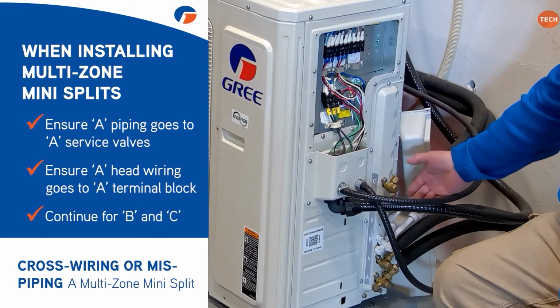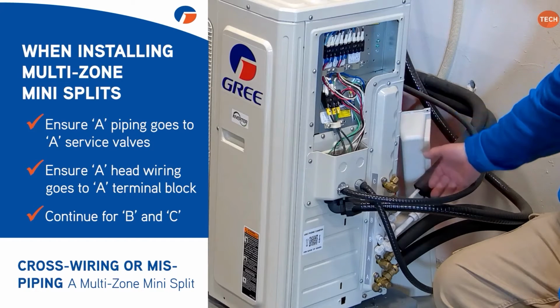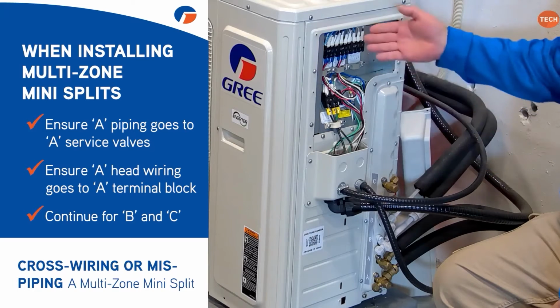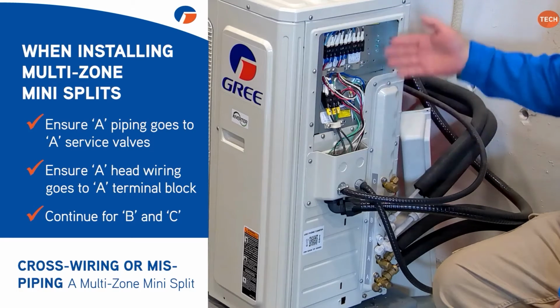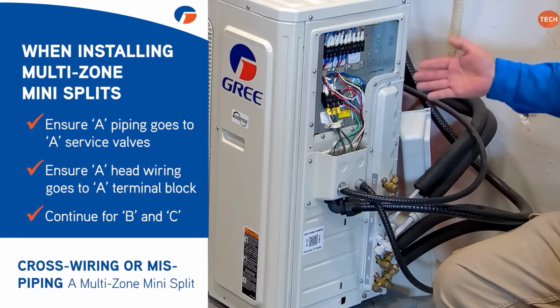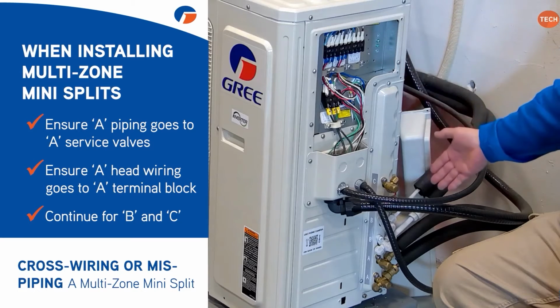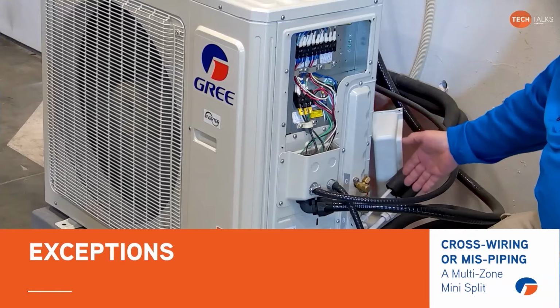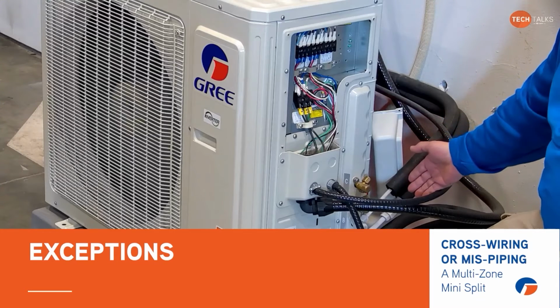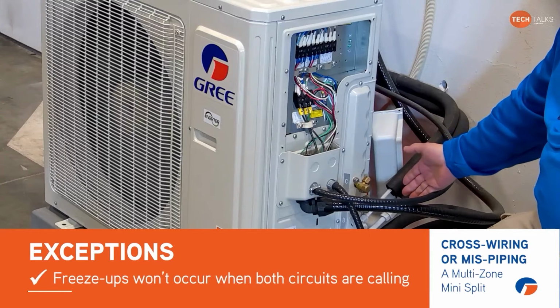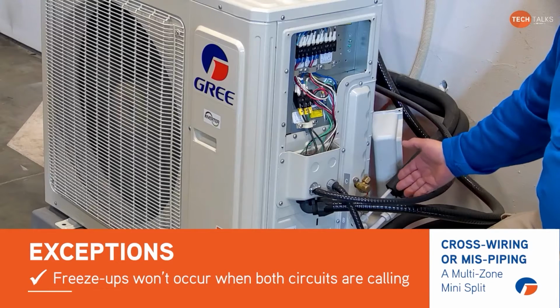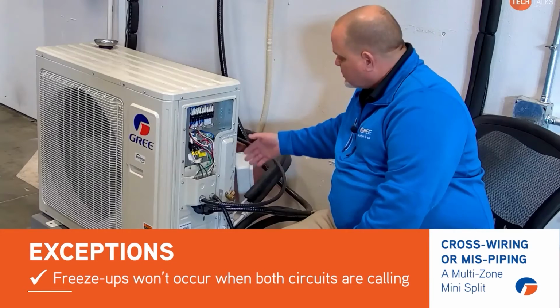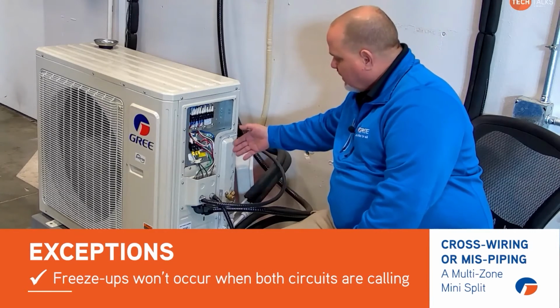And then the B piping needs to go to the B service valves, and the wiring from the B needs to go to the B terminal block. And then the same thing with C. And if you cross-wire those, as I just showed you, you're going to get freeze-ups. Now, if both of those indoor units were calling at the same time, then it won't freeze up because we're controlling the EEVs on both of them. So keep that in mind when you're installing a multi-zone system.